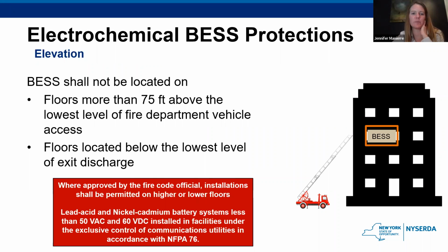Okay, there's an elevation requirement. Energy storage systems cannot be on floors more than 75 feet above the lowest level where the fire department vehicle can access, nor can they be on floors located below the lowest level of exit discharge. This is another one with some exceptions, where the fire code official can approve installations on higher or lower floors based on testing results and if they feel comfortable with the safety features and things like that. Not really an exception, but a different use case that we'll see later is that rooftop systems are allowed, but they have their own set of requirements. But otherwise, inside the building, you don't want them too high or too low to be able to respond to an emergency.